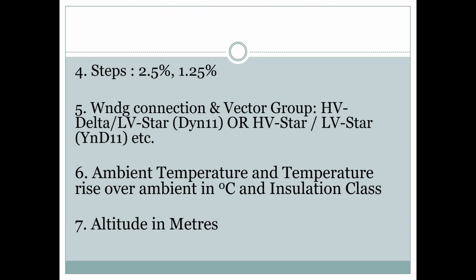The slide states winding connection and vector group. These vector groups have very, very specific requirements for specific purposes, like delta star, secondary star, primary delta. Because of the generation, you are synchronized with the connecting transformers or switchyard, so these vector groups have to be matched. These are in the list. There are so many vector groups, but delta star and star delta are the most common.